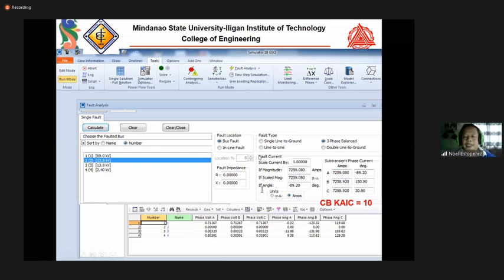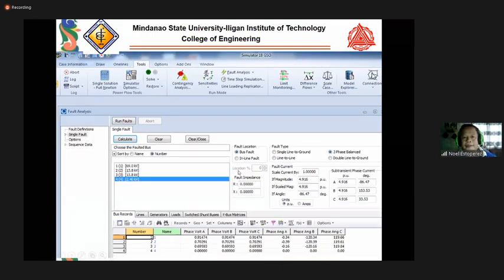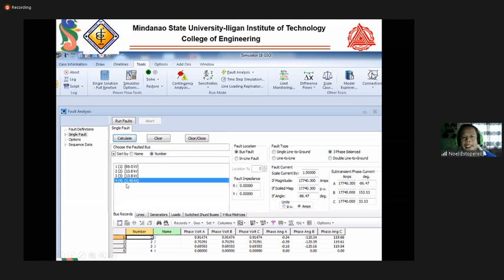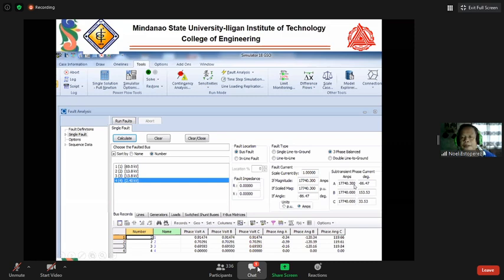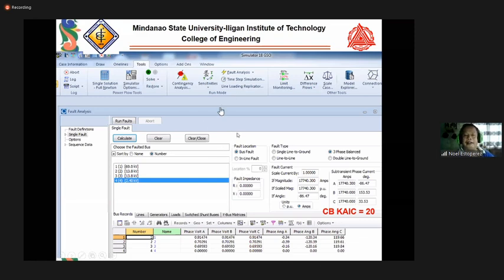So you can select here the available KAIC rating of the CB. I just place here the 10 as our KAIC rating. And then for bus 4, 3-phase fault, we have 17.7. So similarly, it will give us a 20 kiloampere interrupting current.